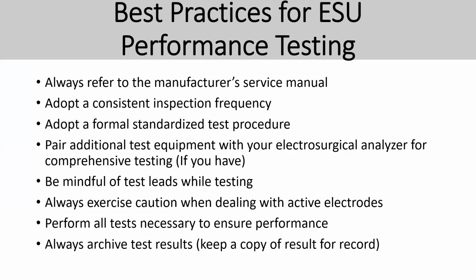Best practice for ESU performance testing: always refer to the manufacturer service manual if you have one. If you don't have one, follow the international standard. Set up a consistent inspection frequency. For ESU, you might do a performance test twice a year, depending. If the machine is always being used or always has issues, you can do it once every 3 months, depending on how you want your inspection plan.